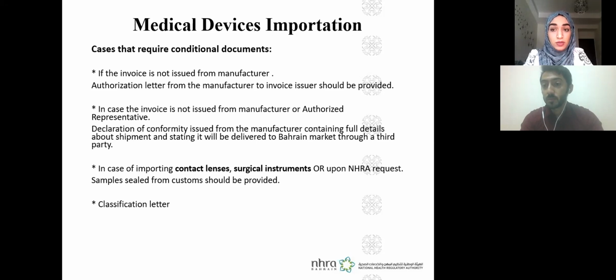Thank you very much. And I would like to add also in terms of post-market surveillance, if the manufacturer does not know that this device is located in Bahrain, and for instance, the device was recalled, they cannot locate where that device is. And if there is any issue with the safety or the quality of the device, patients and end users will still use a recalled device. So we're putting patient life at risk.